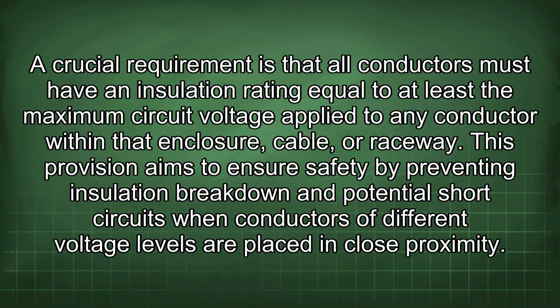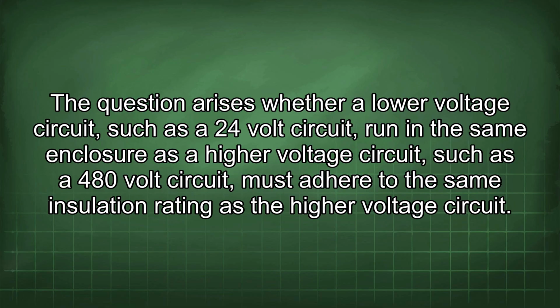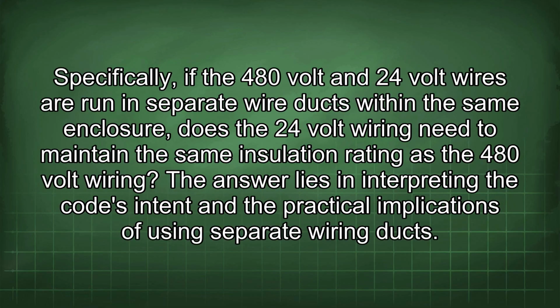This provision aims to ensure safety by preventing insulation breakdown and potential short circuits when conductors of different voltage levels are placed in close proximity. The question arises whether a low-voltage circuit, such as a 24-volt circuit, run in the same enclosure as a higher-voltage circuit, such as a 480-volt circuit, must adhere to the same insulation rating as the higher-voltage circuit. Specifically, if the 480-volt and 24-volt wires are run in separate wire ducts within the same enclosure, does the 24-volt wiring need to maintain the same insulation rating as the 480-volt wiring?